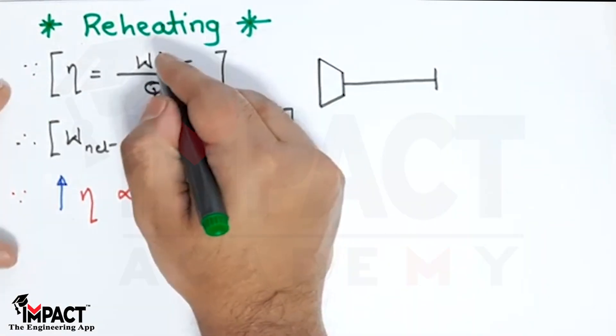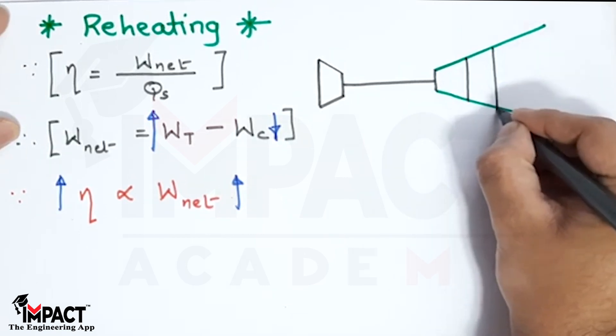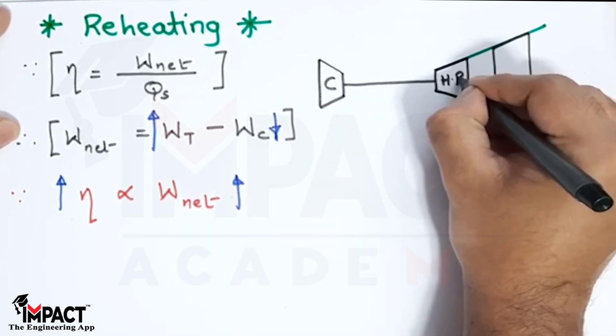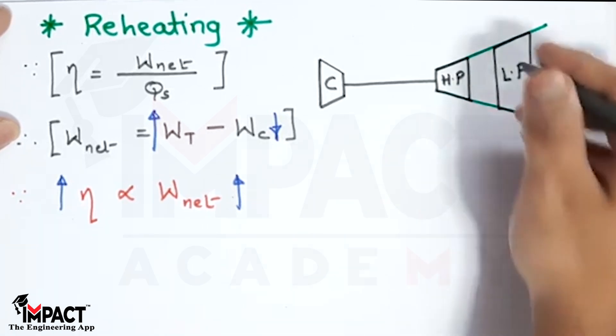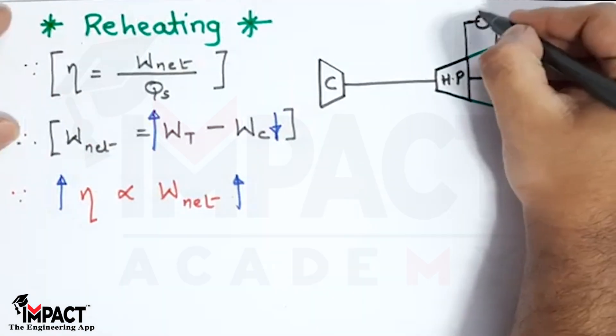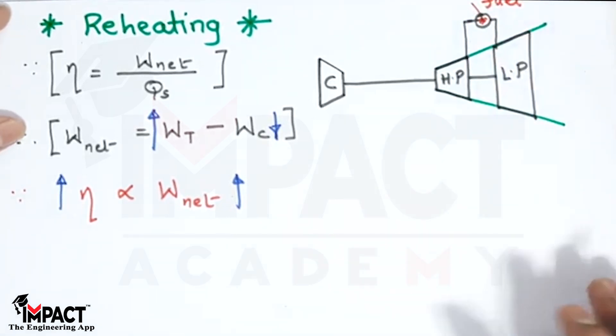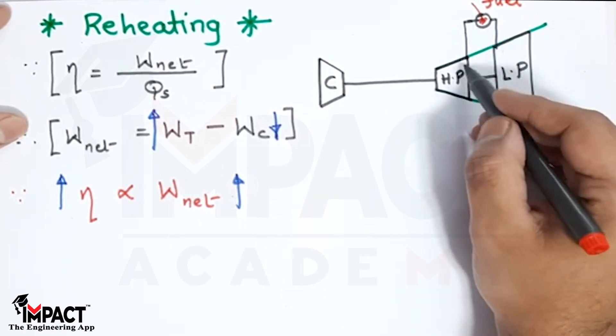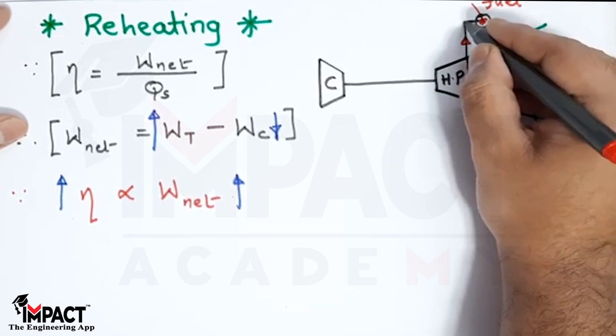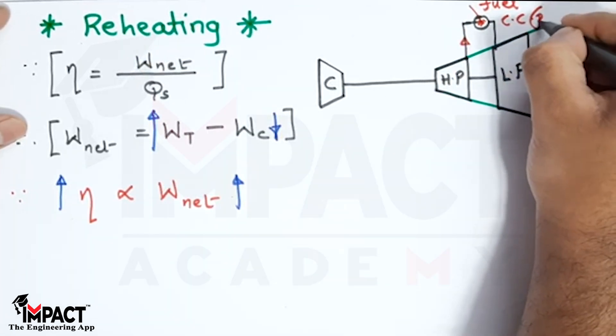When drawing the reheating cycle, you need to draw two turbines. We have the compressor, then the HP (high pressure) turbine, and the LP (low pressure) turbine. Both turbines are connected on a common shaft. Between the HP and LP turbines there is a combustion chamber, where fuel is injected in an open cycle gas turbine, or heat is transferred via a pipeline parallel to the gas in a closed cycle gas turbine.